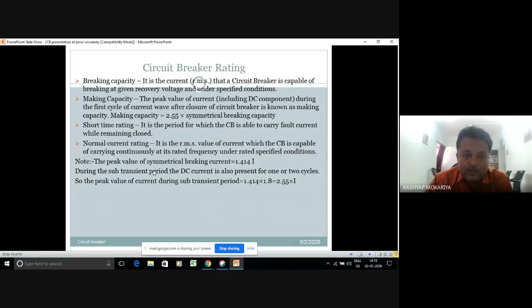I have put one note here. The peak value of the symmetrical breaking current is 1.414 into I. During the subtransient period, when the DC current is also present for 1 or 2 cycles, the peak value of current during the subtransient period will be 1.414 into 1.8. So that will give me the figure of 2.55 I. Through the 3 states your phenomenon will pass: the subtransient, then transient, and the steady state.